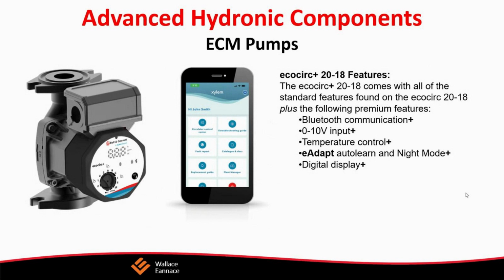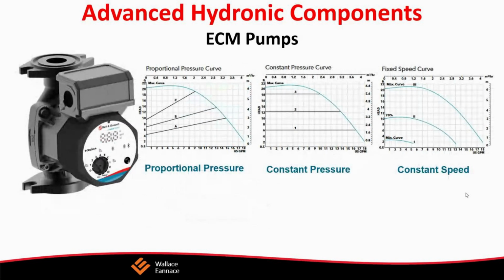You can also set it for constant pressure. It'll speed up or slow down to maintain constant pressure through the system. That's an application used, for example, in pressure boosting, where we're providing water to a system and want to maintain that constant pressure. Or we can set it at constant speed with an adjustable speed control. It operates with fluid temperatures from 14 to 230 degrees F, so it can be used for heating and cooling. And it comes with a Circ Guard, an integrated system that allows for purging of air and prevents deadheading and other system problems.